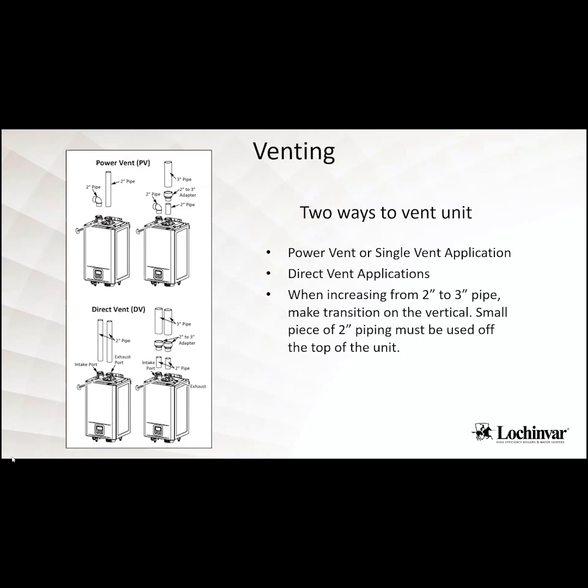So those connections on top of that unit are 2-inch for the intake and the exhaust. If you are going to go to 3-inch pipe off of there, we want you to try to do that within the first 12 inches coming off of that unit. So you can run this unit as a single pipe or a 2-pipe. If you run a 2-pipe, just like any other unit, it's going to breathe a lot better than if you're pulling from different pressure zones.